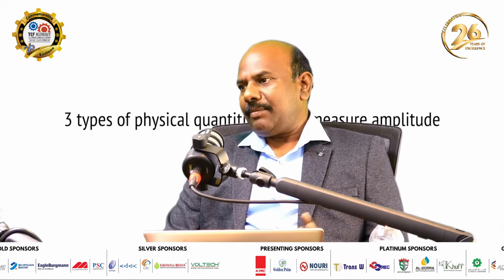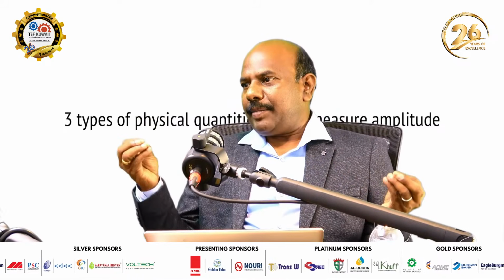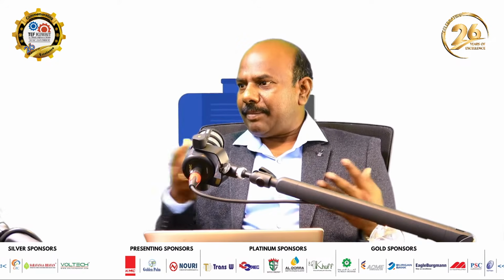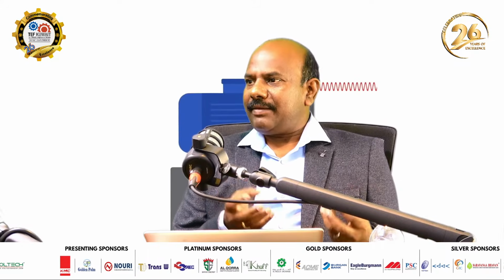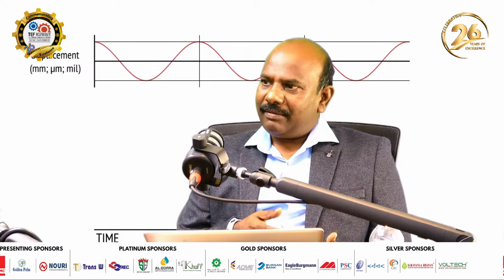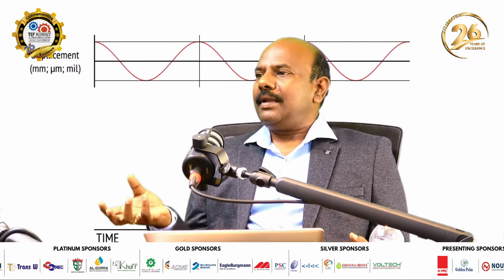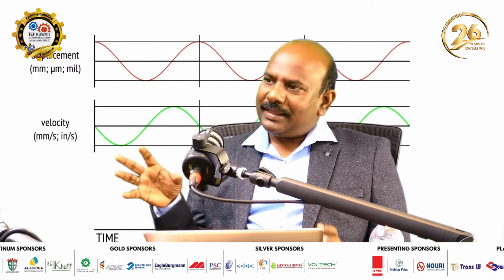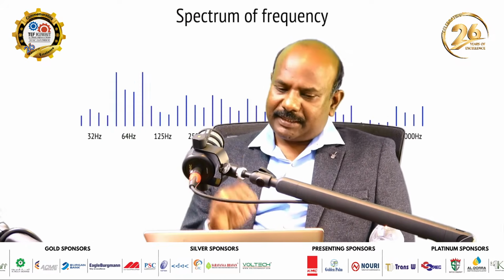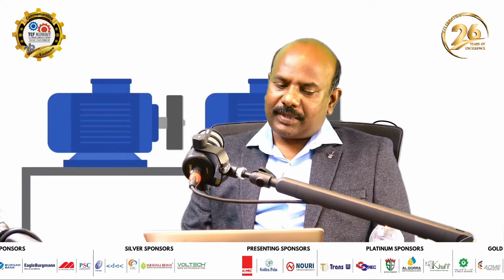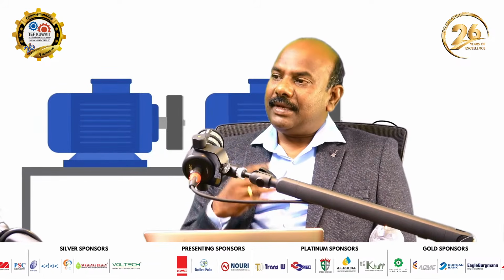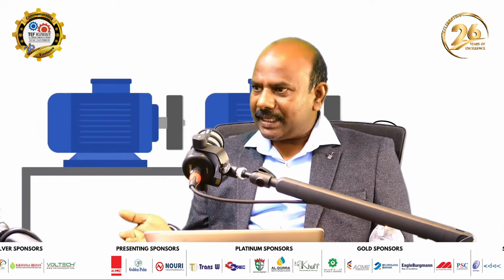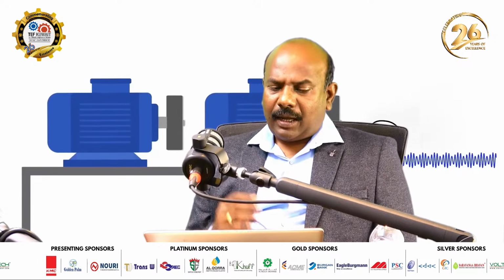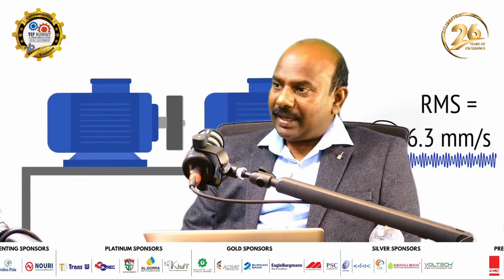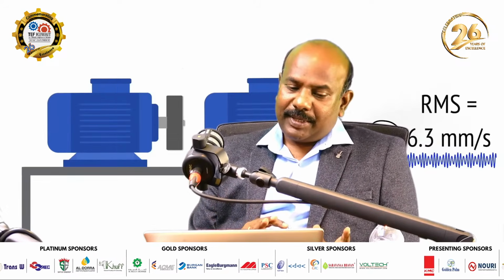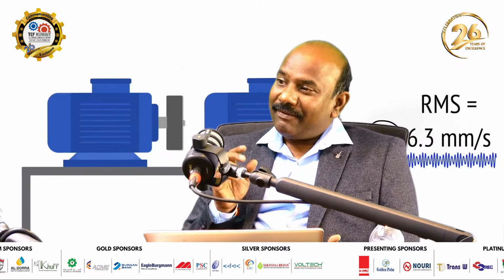See, machine failures are classified based on the type of machine. There are predefined failures available. For each predefined failure, the vibration pattern or spectrum analysis has specific patterns. So the experts will analyze the data, and whenever the values go above the predefined values, they will come into the picture, analyze the higher values, and be able to know what could be the reason for this elevated vibration. By studying the vibration patterns, these experts identify underlying causes of the abnormal vibration, and they will give us a report on what has happened. Maybe it is wear, misalignment, loose components, or process instability. Also, by tracking the vibration values, we can detect gradual changes, and these gradual changes give an indication of the wear happening on the machine.